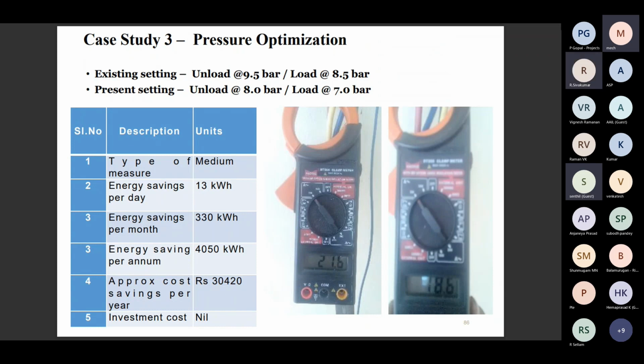Next, pressure optimization. Earlier I told about this pressure minimization. One unit was in the pump industry. They were operating a small 15 HP, 11 kilowatt compressor, loading at 8.5 and unloading at 9.5. With this existing pressure setting, the current taken by the compressor is nearly 21.6 amps. We reduced the pressure setting to 7 to 8 bar, 7 bar loading and 8 bar unloading. So 18.6 amps is the current consumption, so 3 amps was reduced.